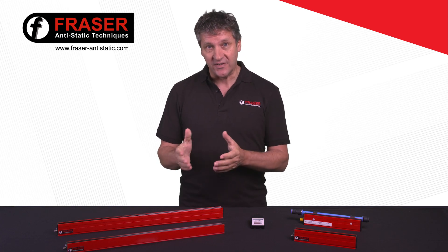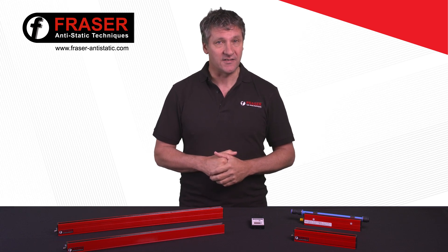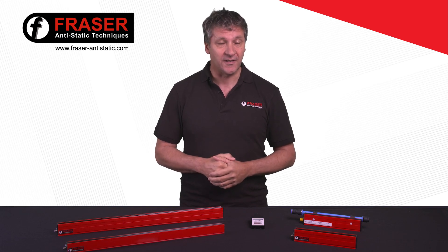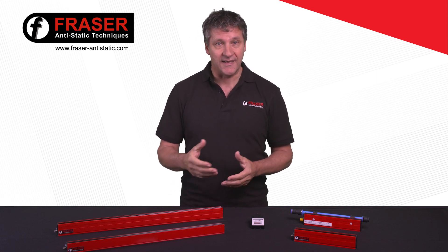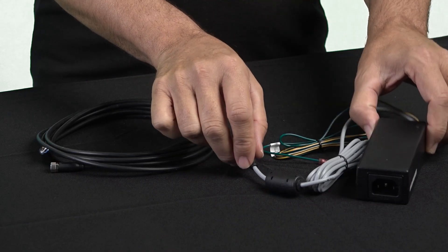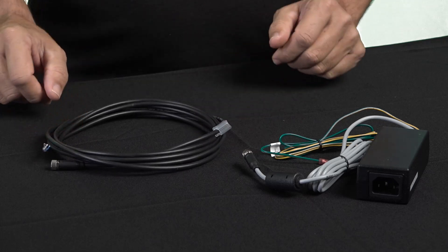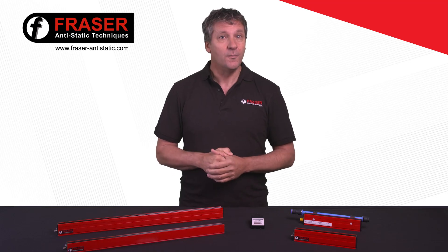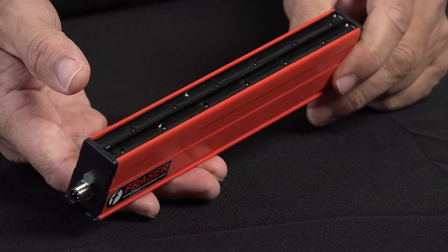Here we're looking at the 3014 and 3024 short and medium range 24 volt DC ionising bars. These offer powerful performance to eliminate static charges in most industrial applications. All of the electronics and high voltage generation are housed inside the bar, so there's no need for separate high voltage power supplies or cables. Power options are a mains laptop style PSU or 24 volt cable connected to a suitable 24 volt circuit or PLC on the machine where the bar is installed. All bars are shockless in operation with fully encapsulated electronics and use long life tungsten emitter pins.